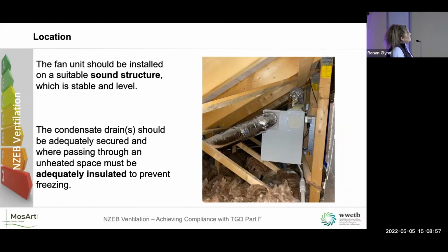So here's another couple of directions out of the installation commissioning guide. The fan should be installed on a suitable sound structure which is stable and level. So that's neither stable nor level. Okay, it's dangling there on one timber. The condensate drain should be adequately secured where it's passing through an unheated space, and it must be insulated to prevent freezing, not a screed of insulation on that. So I had a chap in my class and he was saying his unit shut down because the condensate drain actually froze in the attic. So he didn't have adequate insulation on it. So that's really important.